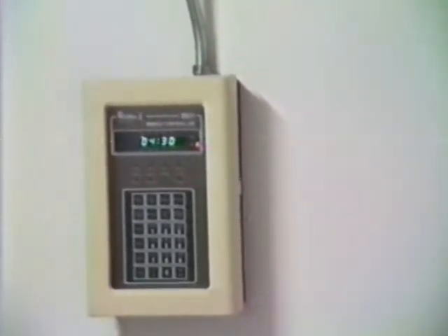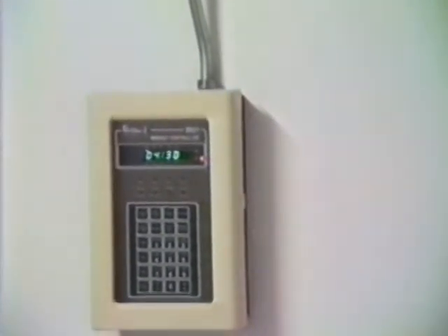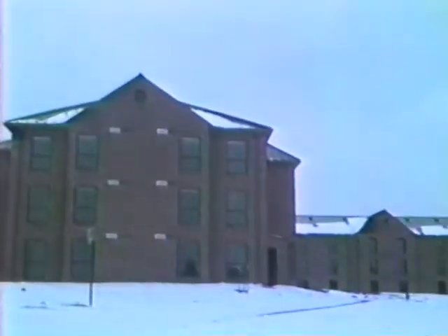In addition, this controller has the ability to sense the outside air temperature as well as the inside room temperatures and compensate either earlier or later for system startup, depending on what the system needs to do at that particular time. The programming of this is done easily from inside. The control manuals, which we have left with you, give step-by-step instructions on how to program this controller.